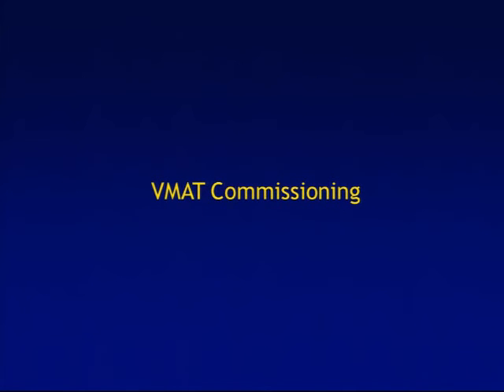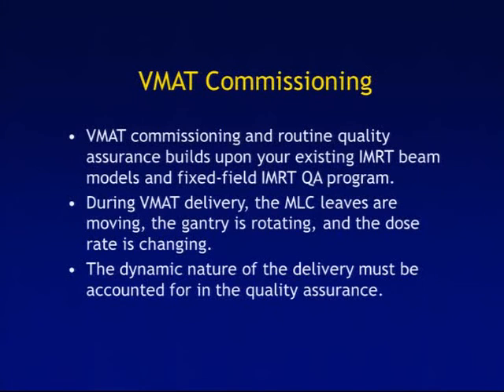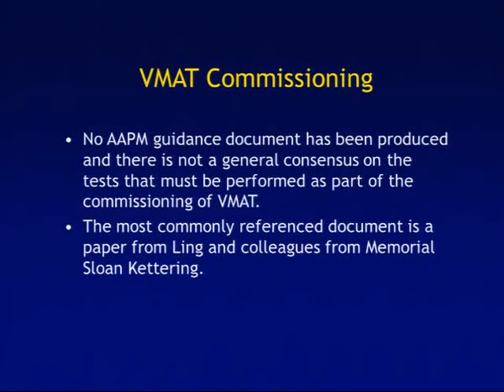How do you go about commissioning a VMAT system? VMAT commissioning and routine quality assurance builds upon your existing IMRT beam models and your fixed-field IMRT QA program. During VMAT, the MLC leaves are moving, the gantry is rotating, and the dose rate is changing. The dynamic nature of the delivery must be accounted for in your quality assurance. To my knowledge, there's still no AAPM guidance document, and there's not a general consensus on the tests that must be performed as part of VMAT commissioning.